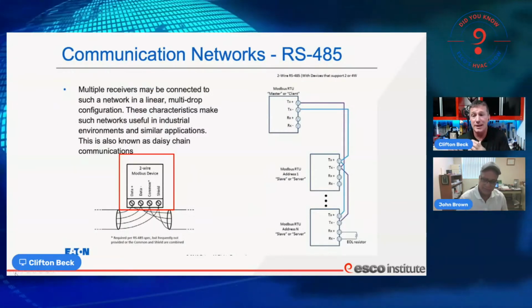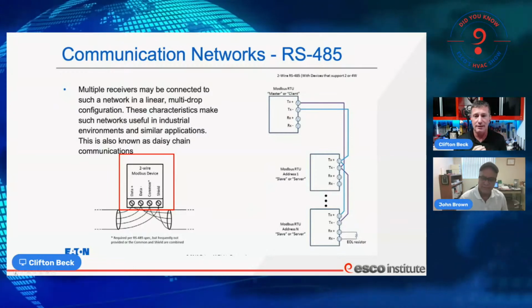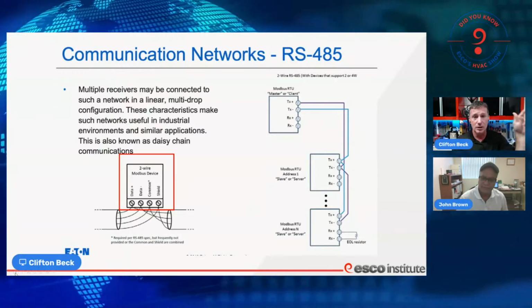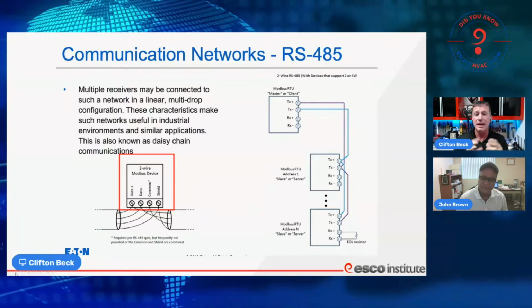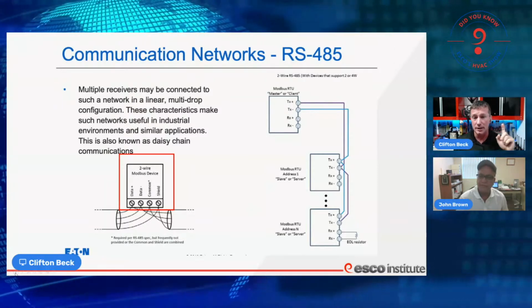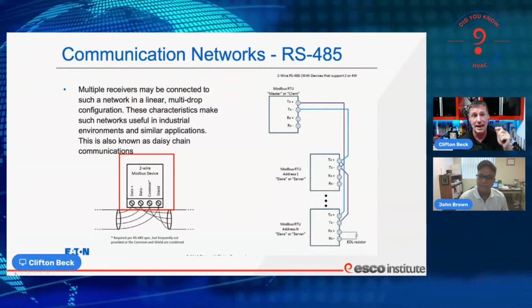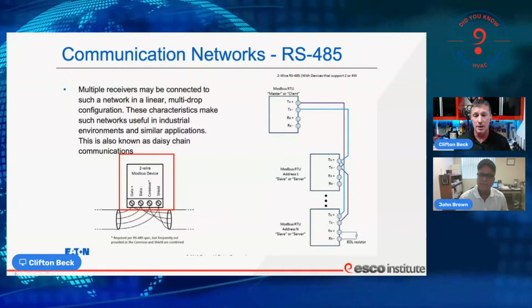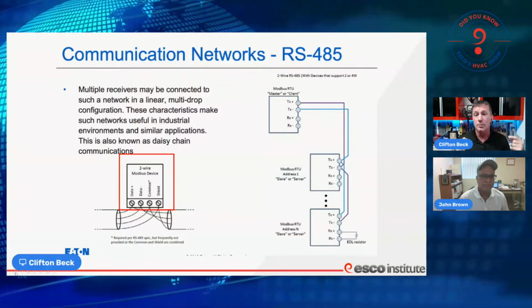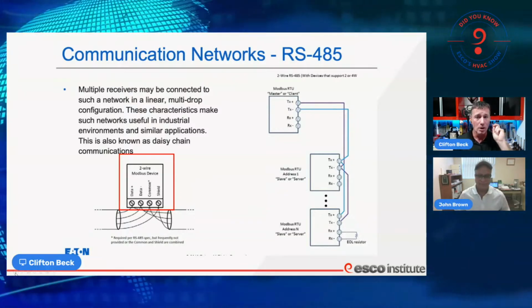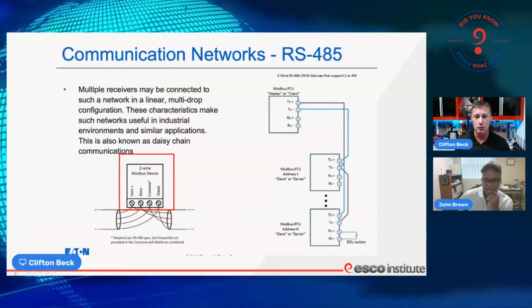If we reflect back on this RS485 platform, we can see in the little red square that it is primarily a two-wire data function. We'll call it data plus and data negative. Then we might have our common and our ground, which is for our communication cable, but the work is really being done on those two terminals.